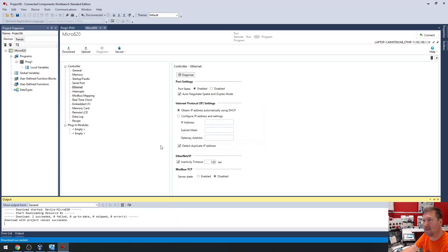And then all of a sudden I can't communicate with my PLC. It's going to say that download the project value succeeded, but we're not going to get that normal connected, or mainly our little run thing here is never going to indicate. And the problem is we have just set our PLC to DHCP.